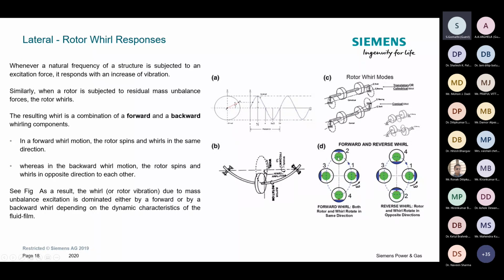Similarly, if it is vibrating like this, continuously moving like this, then if I put a probe when the rotor is over here, maybe it's zero or a minimum negative distance from this point - it is negative distance - and when it passes to here, it may go to positive distance. So if I put a probe over and over here, I will get two different sinusoidal waves, and the amplitude of that depends upon how much whirling happens.